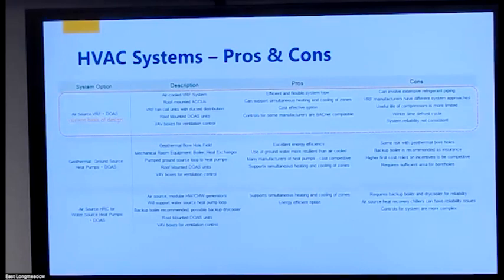Each of these three systems is being modeled in our energy modeling software to estimate their annual consumption. That gets factored into a life cycle cost analysis, so we can factor in not only the first cost for installation, but the annual operating costs, maintenance costs, and life cycle costs. So if over a 50-year period we end up having to replace certain equipment, we'll factor in those costs, and then look at each of these three options as a total cost of ownership over a 50-year period in net present value terms.